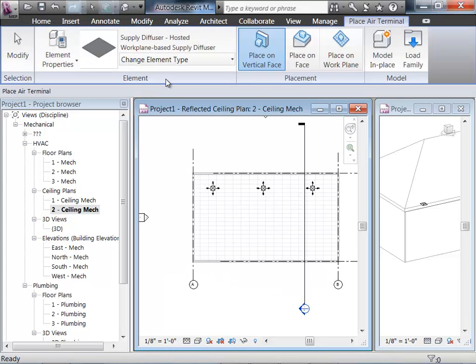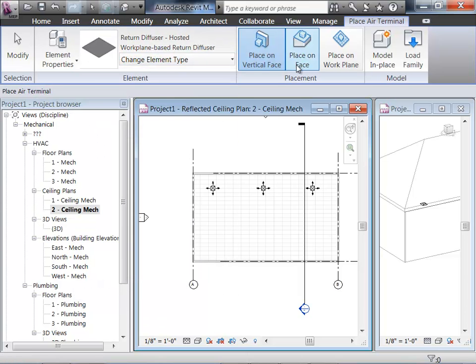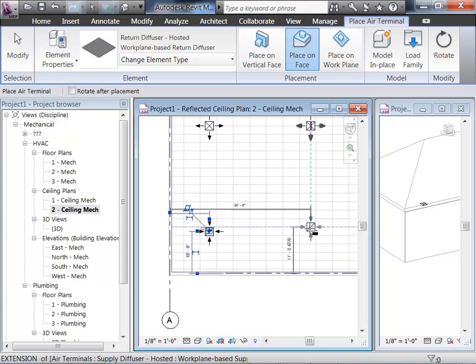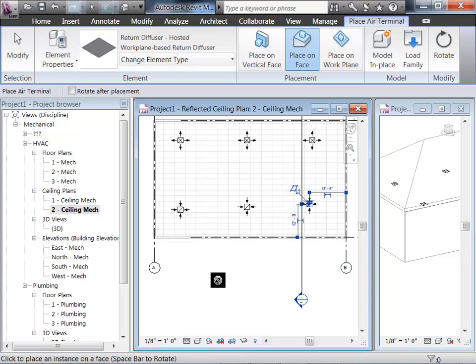Now I'm going to go ahead and place some of the return diffusers, again using the hosted ones. Place on face, and we'll just put them on the other side. There's a whole science to where you place diffusers — this is not that class — but as long as you have somewhat evenly spaced supply and return diffusers, that's okay. Typically there's more supply and less return. In this room, for example, you can see that little grate — that's a return. The supply air is provided by active chill beams: there's a connection above them and it's blowing fresh air down. Six versus two, but that's pretty typical.